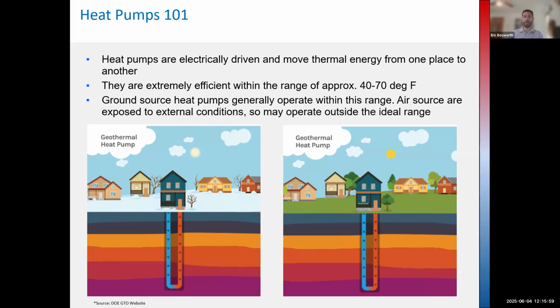The challenge, especially in a climate like mine, is winter—when it's 30, 20, or 10 degrees outside. Now the heat pump is trying to pull thermal energy out of that 10-degree air and push it into a building, and efficiency drops accordingly. You get very low 1.5x efficiencies in the cold winter or the middle of peak summer days, because of that thermal gradient that has to be overcome.